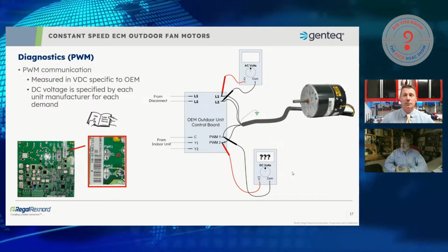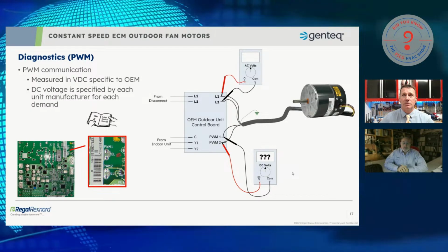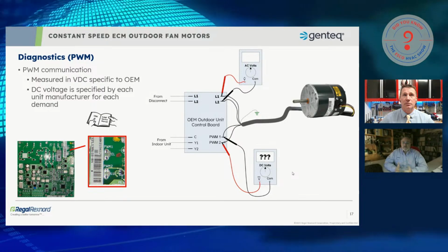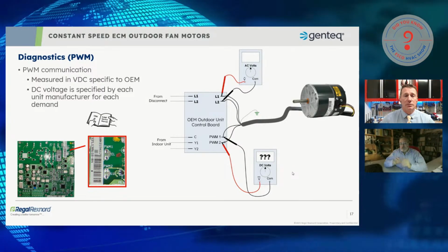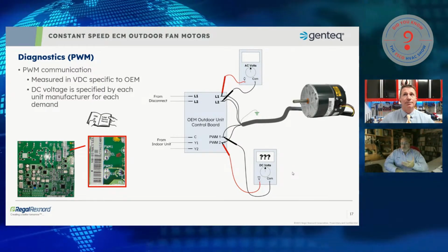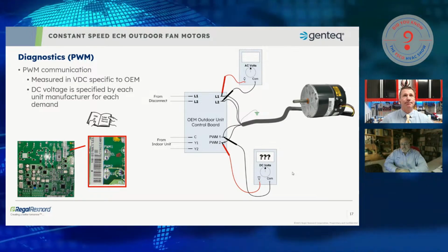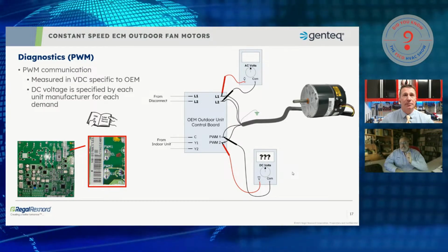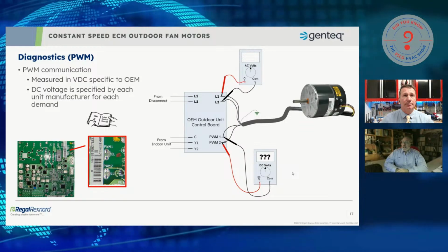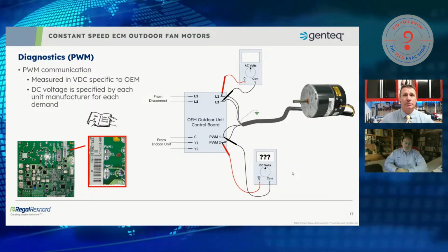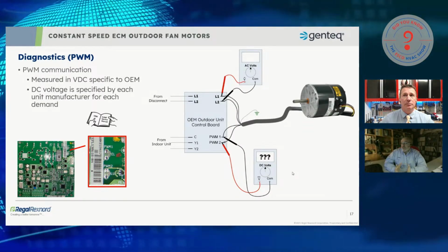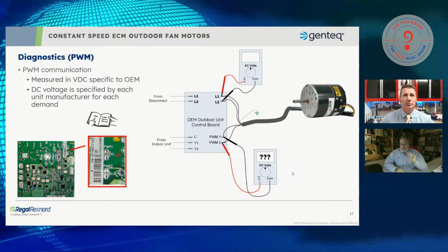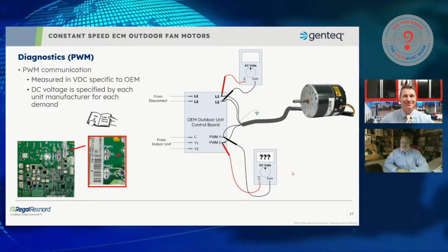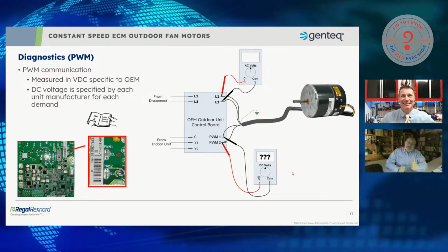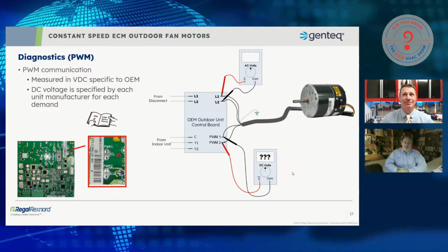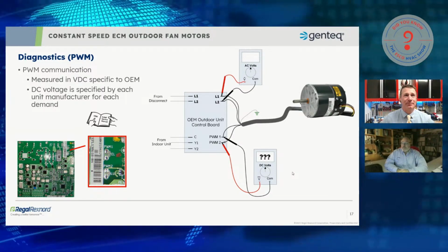And probably the most cumbersome part about diagnosing a PWM system is there's no one set of values. It's not the typical 24 volts AC, or what you may see on some systems, 18 volts DC, which is a very common DC signal voltage that gets used. This PWM signal voltage could literally be anywhere from 2 to around 20 volts DC, and don't write that down and say, okay, it's always going to be between 2 and 20 volts DC. It could be a little lower, it could be a little higher. It's all dependent on how the OEM wants to develop that signal.